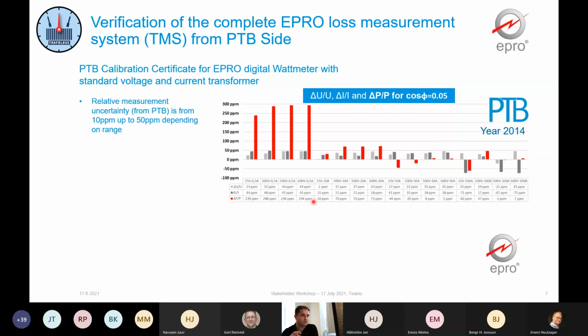And to cover a wide range of power measurements, all voltages were measured with all currents. In sum, it was 60 combinations of voltage and currents. For example, here the first combination in the graph is 25 volts and 0.5 amps. And at the end, the results show that the maximum error is below 300 ppm for power measurement at power factor 0.05. The relative uncertainty from the PTB was, depending on the range, 10 ppm up to 50 ppm.